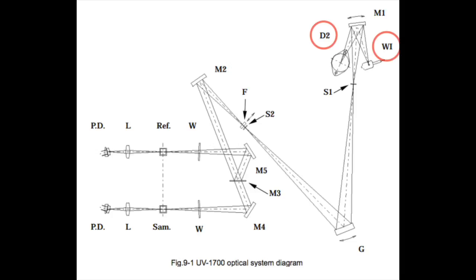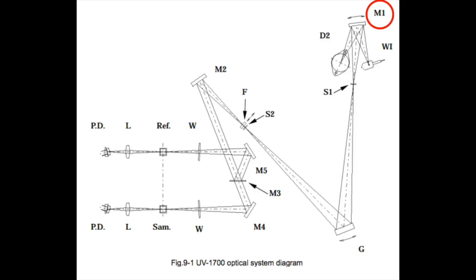The light is emitted by a halogen or a deuterium lamp depending on your selected wavelength. In this case, our wavelengths are within the visible spectrum utilizing the halogen lamp. The light is reflected off of the switch mirror, which rotates automatically in response to the set wavelengths.